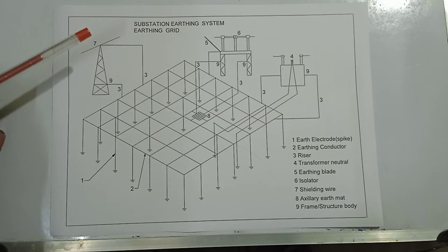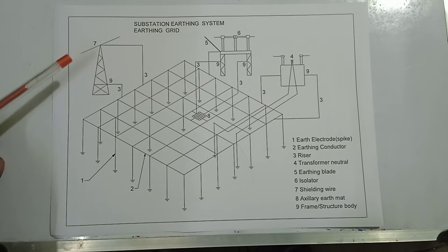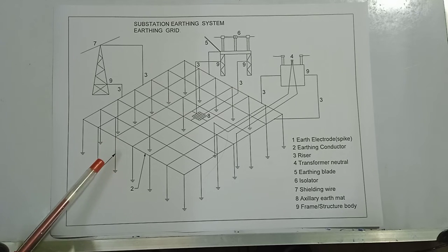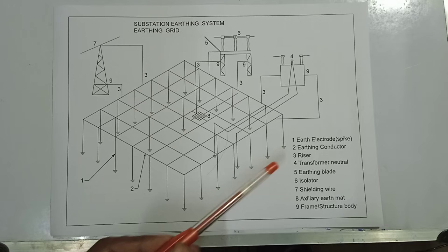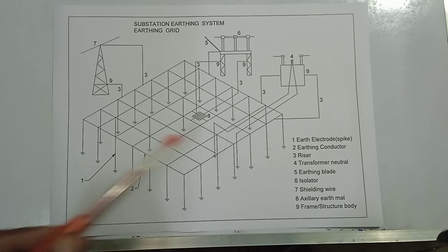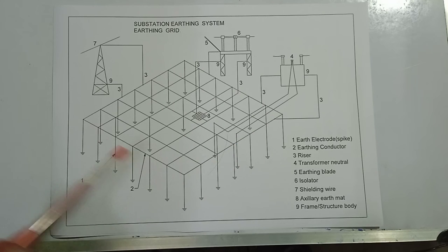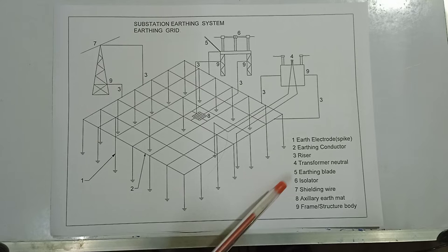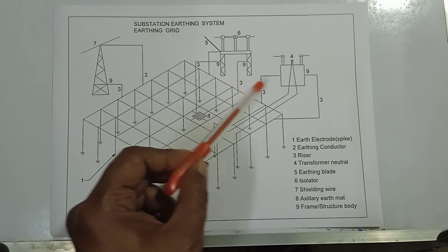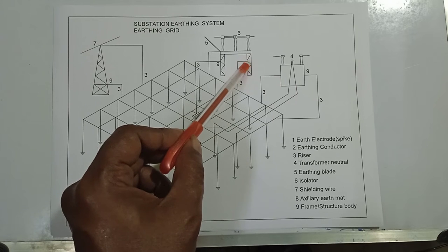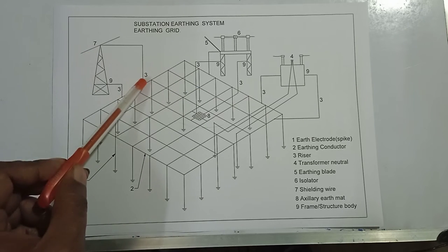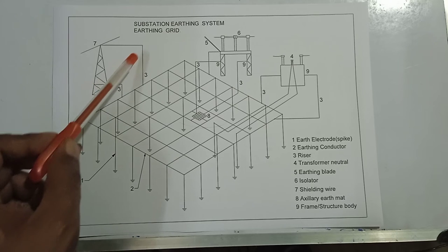Here is the substation earthing system earthing grid diagram. The first component is the earth electrode spike, vertically buried in the ground. The second is the earthing conductor — the grid is made of horizontal conductors in the X and Y axis. The third is the riser, which connects the earthed tank and isolated structures from the grid. One riser is connected to the tower and another to the earth shield.